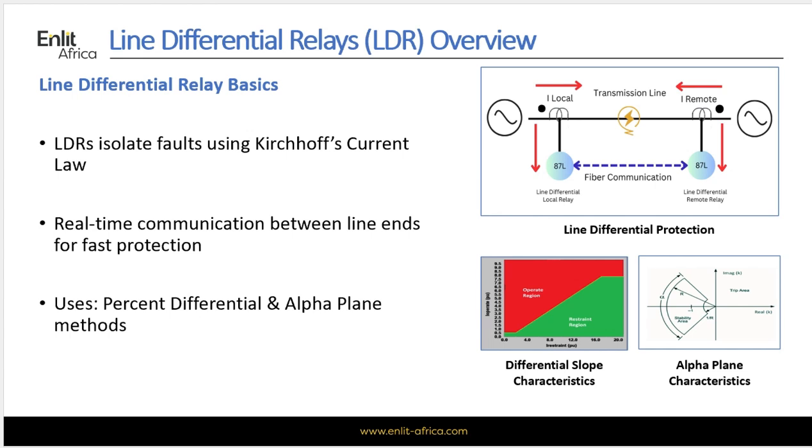Here we see how LDRs use synchronized current data to identify internal versus external faults. When the current differential exceeds a certain threshold, protection is triggered. This is the core of line-based protection schemes.